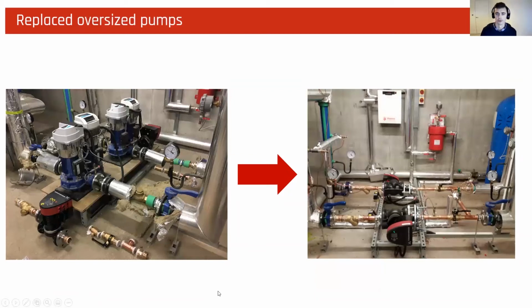Moving on to the plant room, one key aspect of the works was replacing the oversized pumps. Now, this is a great pre and post works photo. It is quite striking to see how oversized the pumps were originally. And as you can expect, we found that the pump electricity consumption on this site was very high. But another key point to note here is that even though we're replacing the pumps with smaller pumps, the smaller pumps are still more than enough to maintain the required performance and reliability of the heat network.